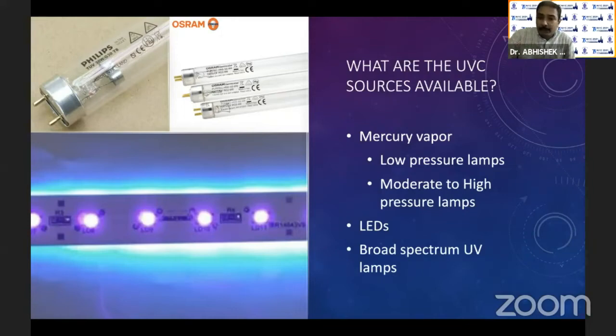There is another very important property of the glass in proper UV tube lights. This glass allows only the germicidal UV to exit, whereas it traps the even shorter wavelengths. Why is that important? Because even shorter wavelengths cause ozone formation. So if all the radiation is coming outside, you will have ozone formation inside the room, which is unhealthy. It can cause upper respiratory tract irritation, and it can cause diseases also. That is why they say that if you've kept a room closed with UV light on for more than an hour, you're supposed to ventilate it for about 10 to 15 minutes before you start using it.